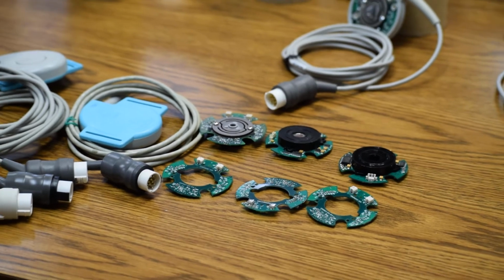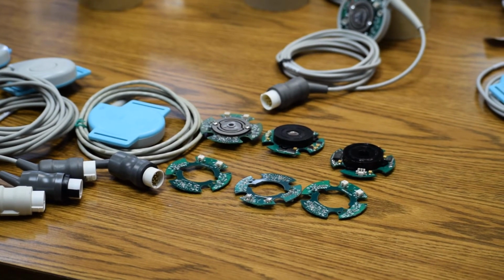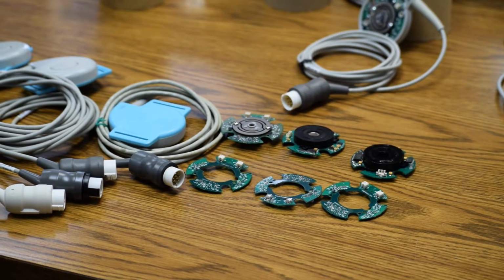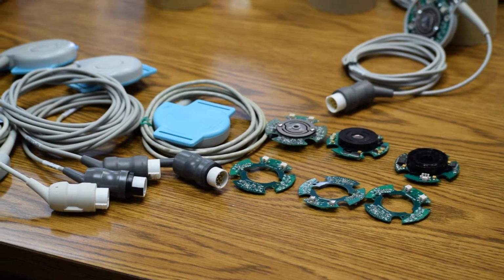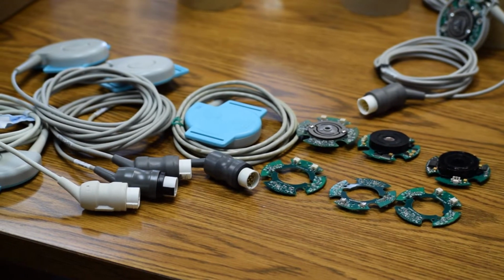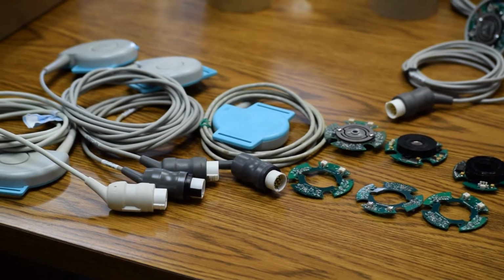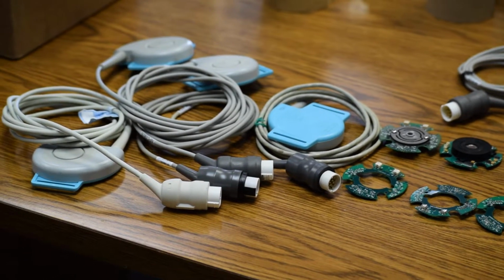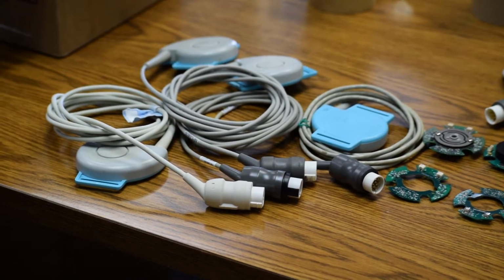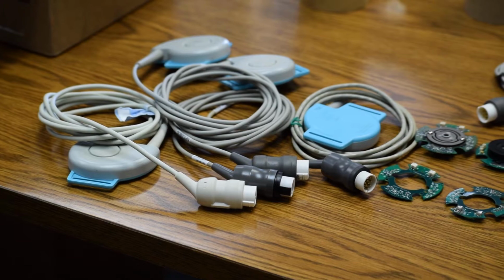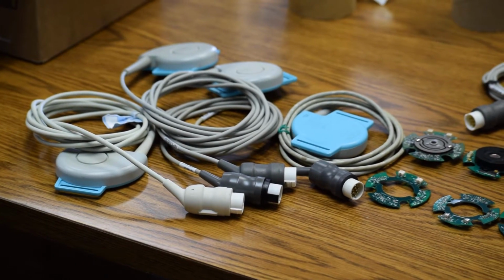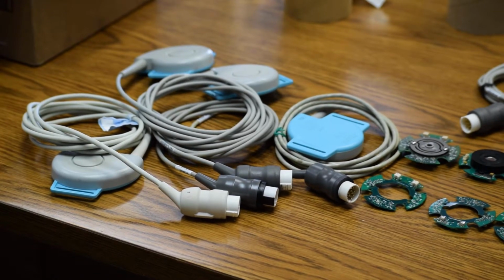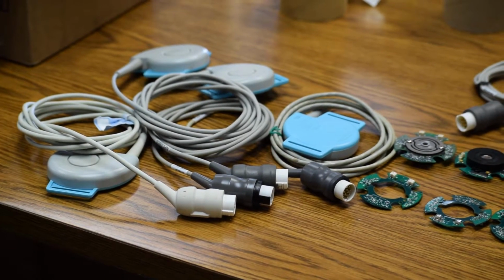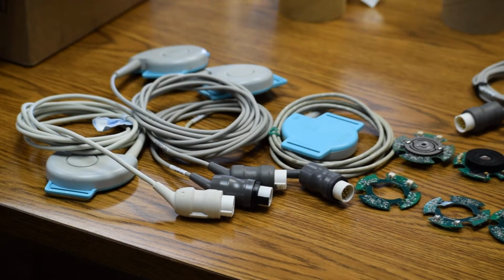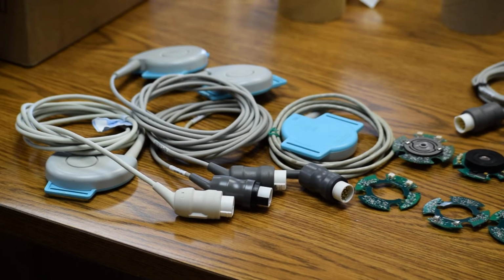One of the biomed technicians pointed out that there are some OEM medical devices with molded connectors functioning well to respective OEM specs. Then the question is why GE Corometrics fetal transducers repaired, or compatible units with molded connectors, aftermarket connectors, do not perform well at all. The answer is yes, it is very much possible if the molded connectors are manufactured with exact same or higher manufacturing standard, with precision tooling and using superior plastic resins. In fact, molded connectors can be made far superior as compared to original GE, provided the resin uses high performance polymers such as PEEK.